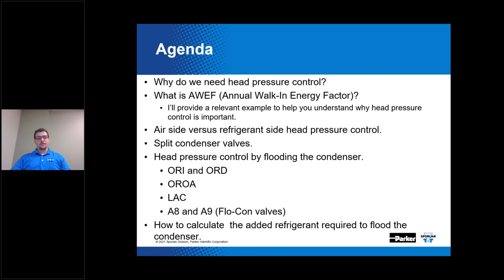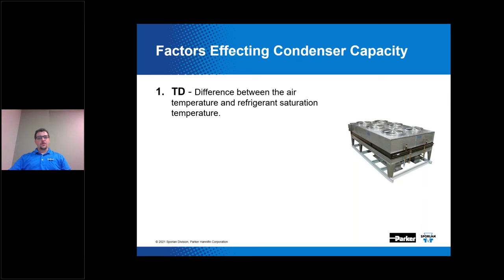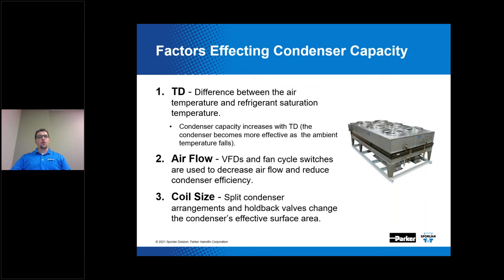There are three factors that affect condenser capacity: your TD, your airflow, and your coil size. TD is the difference between the air temperature and the refrigerant saturation temperature in the condenser. As your TD increases, your condenser capacity increases as well — the condenser actually becomes more effective as your ambient temperature falls, because as ambient temperature falls, TD increases.